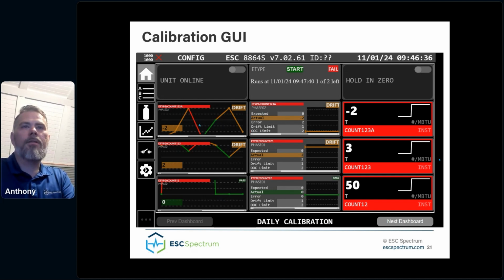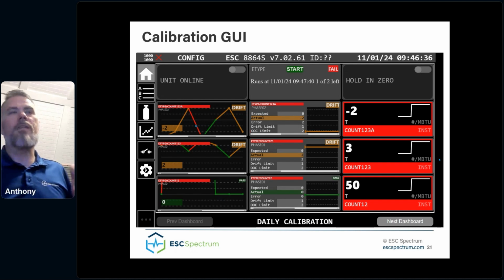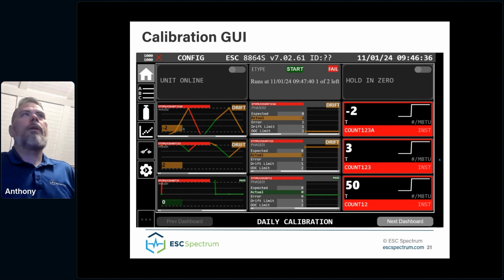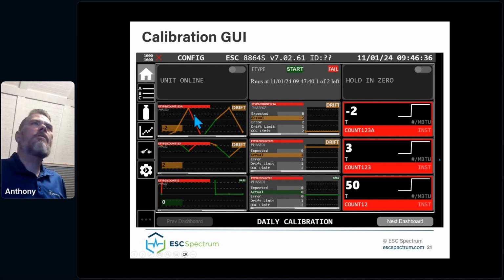The trend view y-axis is based off the largest configured out of control or maintenance limit. If neither one of those are configured, it'll scale to the largest actual value. If the last data point is off the graph, then the text in the middle of the screen will indicate that. And you can swipe again on the front panel to switch back and forth between the two. You can see that the color represents red for out of control, orange for maintenance, and green for passing. And you can see that this data point up here was a drift, and then it went to an out of control point that was off the graph. And so the color of the line represents the status that it's going to. And that's pretty much everything for the drift view.